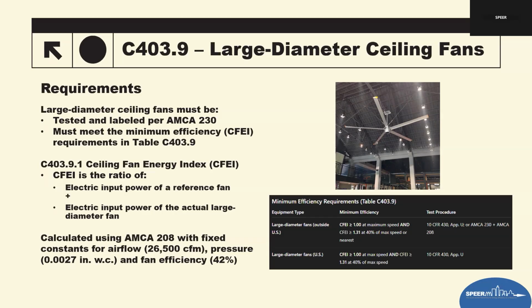So, testing and label requirements. All large diameter fans must be tested and labeled using AMCA 230, which is an industrial standard method of testing fan performance. The fans must also meet the efficacy thresholds listed in table C403.9, the minimum efficiency requirements. The code requires 2 performance checks.